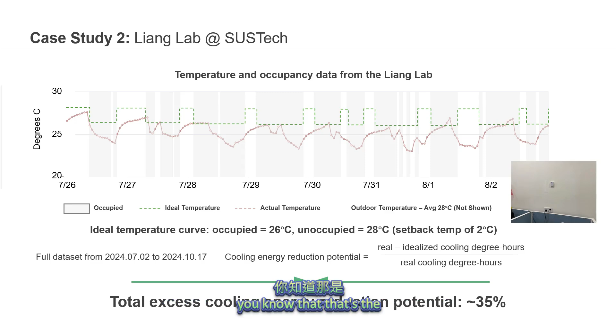So ideally, you would have the temperature at 26 when there's somebody in the space, and at 28 kickback when there's nobody in the space. This red line is the actual. So there's all the space between the idealized and the actual - that's the potential for savings, and that's about 35%. Whether we can actually control on this very orthogonal line, that's not possible, but that's the room that's available there.